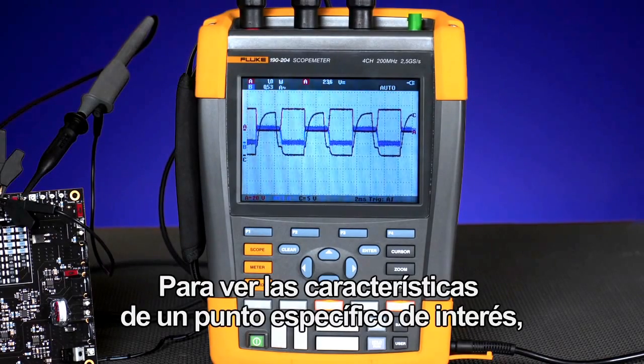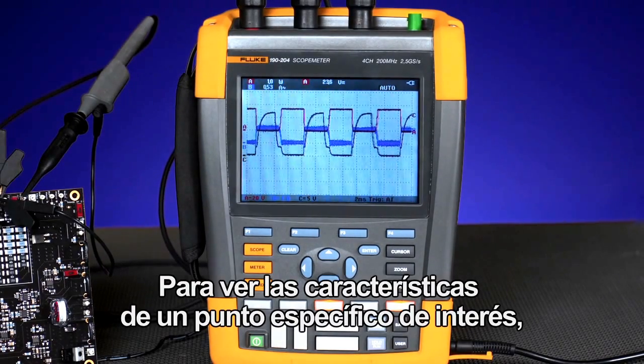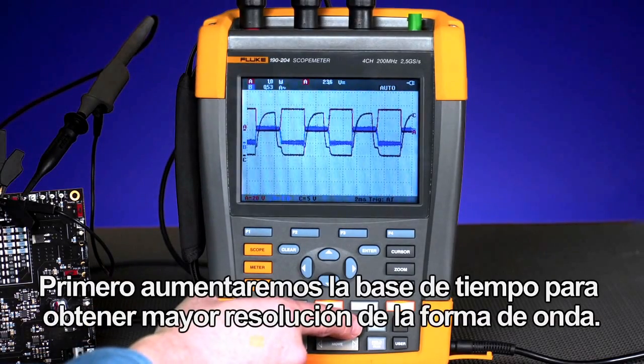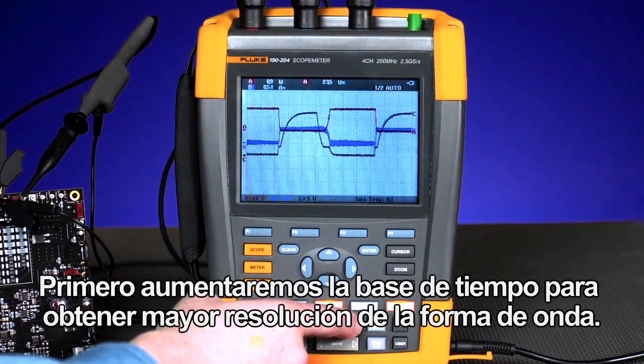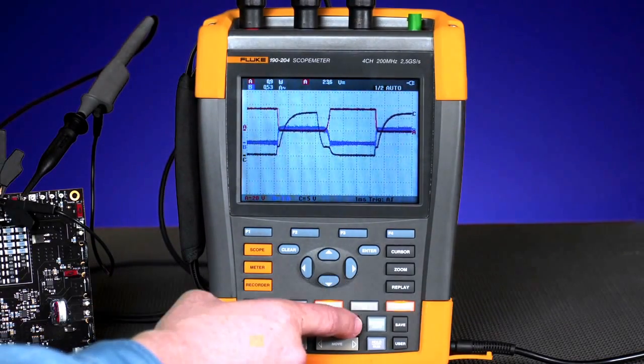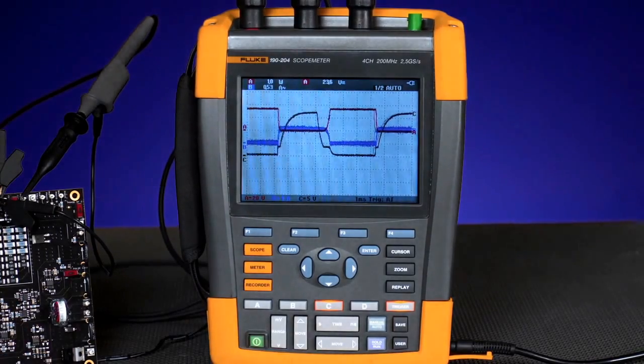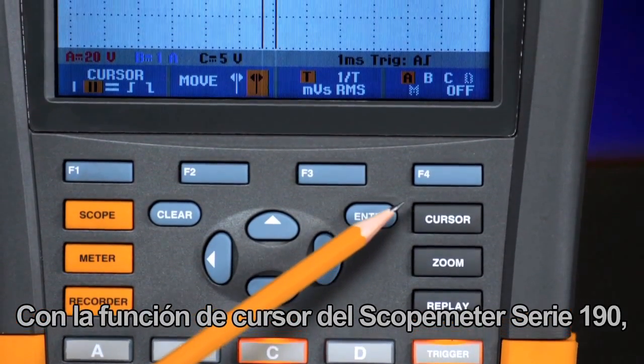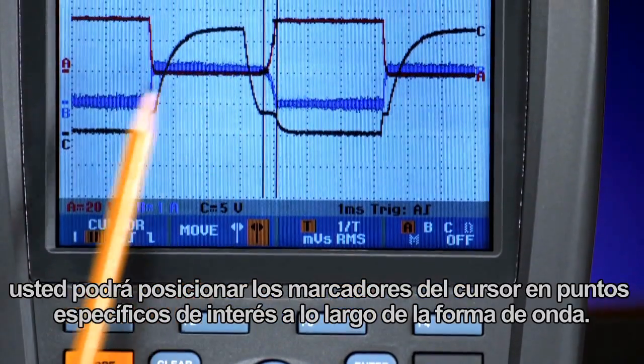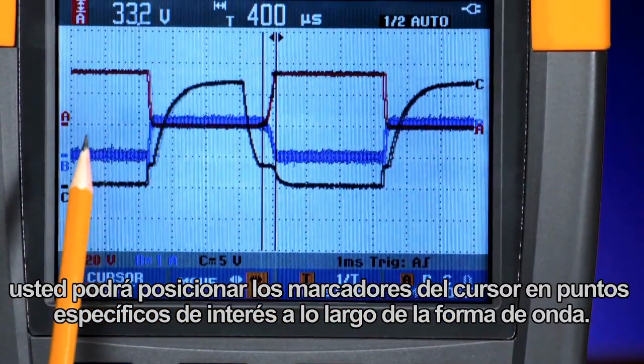To view the characteristics of a specific point of interest, we'll use the cursors. First, we increase the time base to get a much higher resolution on the waveform. Using the cursor function of the ScopeMeter 190 series, you'll be able to position cursor markers at specific points of interest along the waveform.